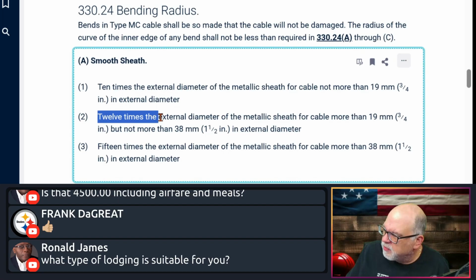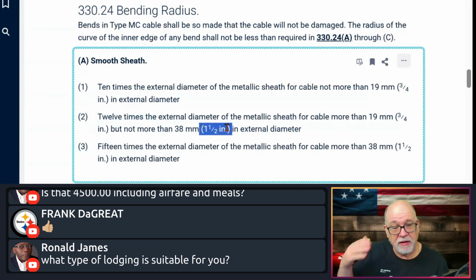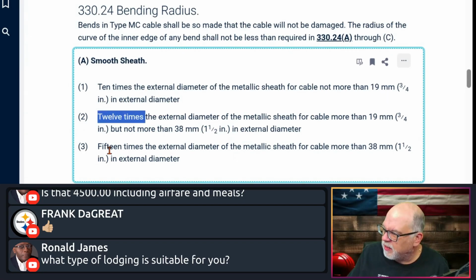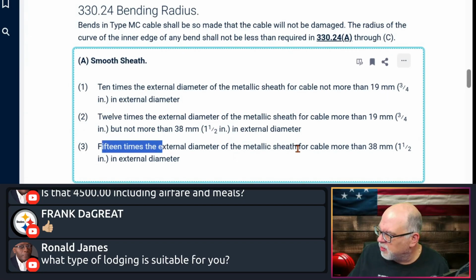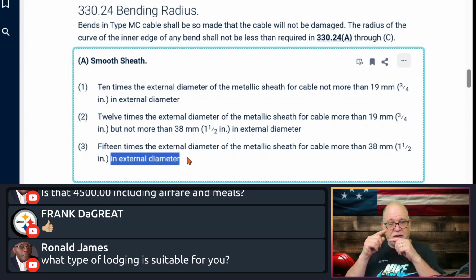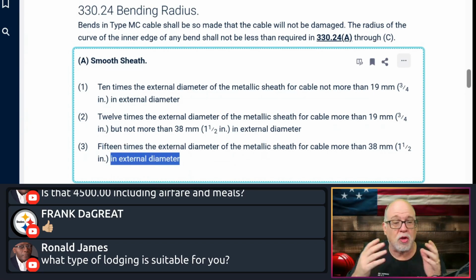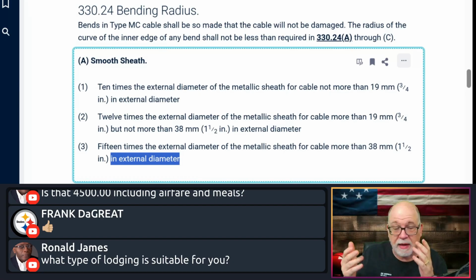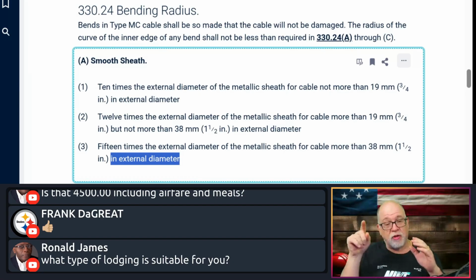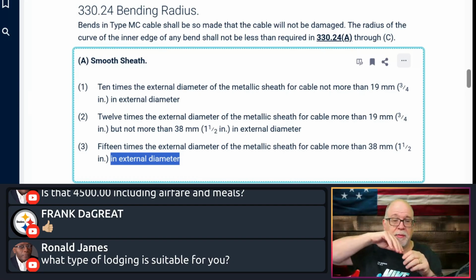So it's 12 times if it is more than 3/4 inch but not more than 1.5 inches. And then 15 times if it is more than 1.5 inches in external diameter. You get that from the manufacturer. You take that value and multiply it by either 10, 12, or 15. That gives you a certain number of inches, and you have to make sure you are not exceeding that radius.